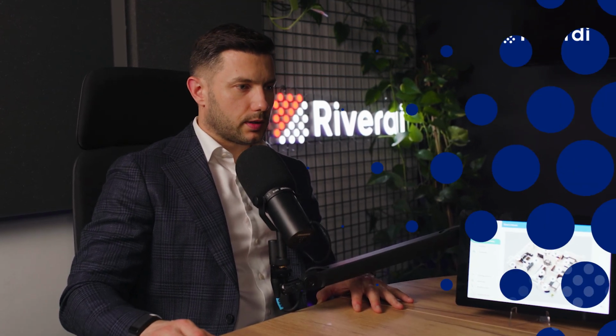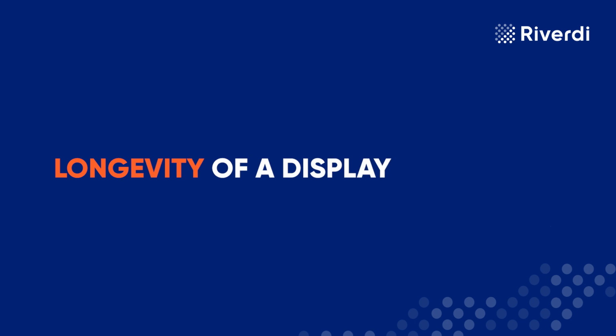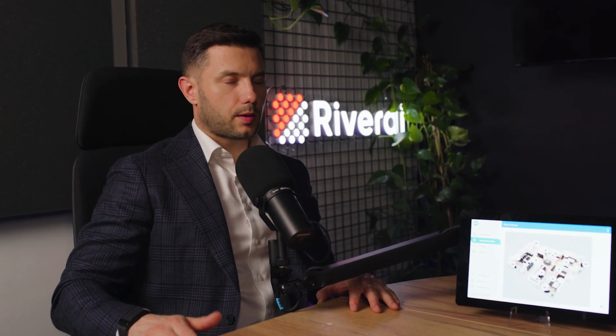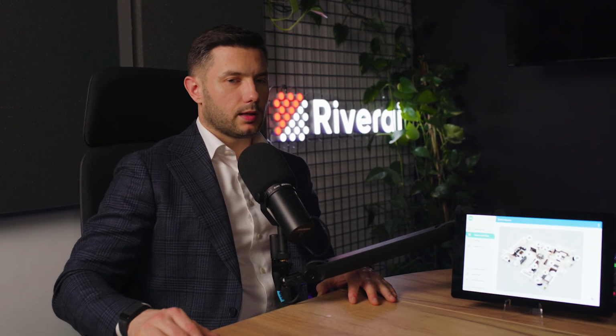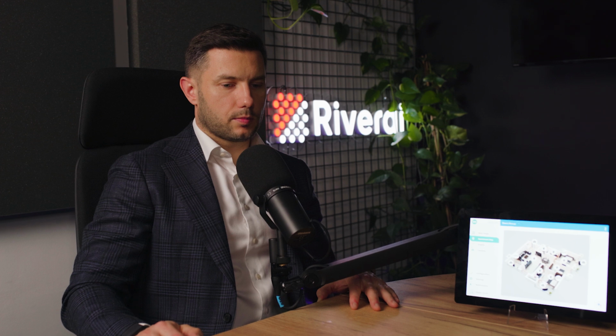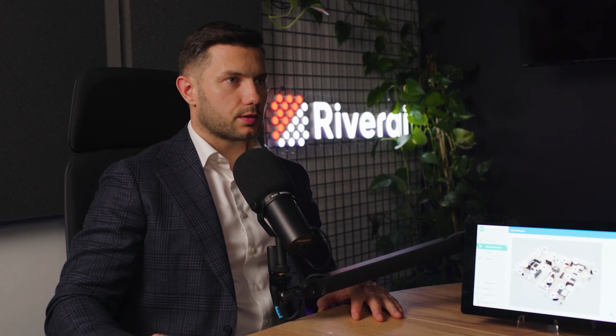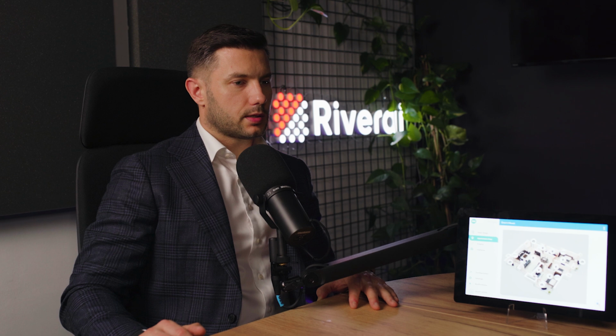And the last thing I would look for in a medical device is longevity. It's how long this display will be available. In most cases, when we work with our customers on medical devices, we typically work maybe 2-3 years, up to 5 years on the project before it enters the mass market. And then when it enters the mass market, most customers expect to manufacture this device for 10 years or even longer. So you need to select a display that will be available for a very long time. That's the typical mistake.